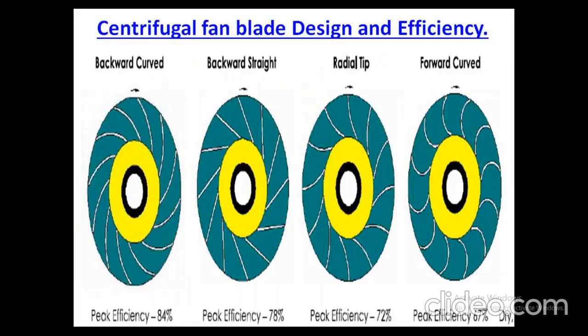There is a change happening in the building segment, and I will also see it in the textile mill. People say, let us go for EC fans, electronically commutated fans, and backward curve type. That can give straight away 20%. But on the existing machine also, you can achieve that same 20%. You can see the impellers. 9 out of 10 textile mills are using this backward straight impeller only. The efficiency difference between a backward straight and a backward curve is almost 6%. This is a straight away visible loss happening in each and every textile mill.